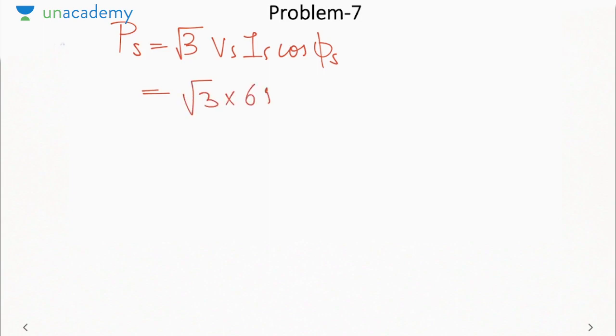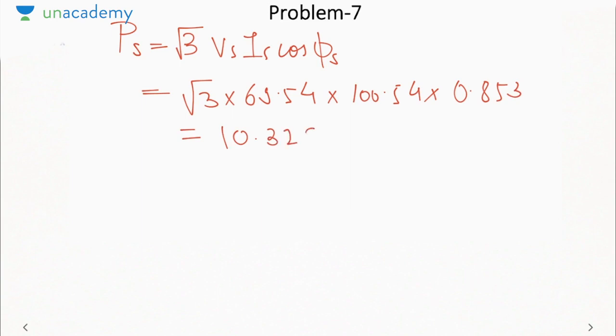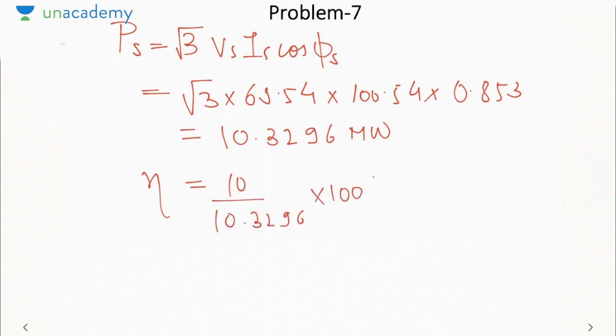Then to find out efficiency, we need sending end power, which is root 3 Vs Is cos phi s. So if you use line voltage, use root 3, otherwise 3. So I am using line voltage into 0.853 lag. So this will be 10.3296 megawatt. So efficiency will be output, that is PR upon PS into 100%. So this comes out to be 96.8%.